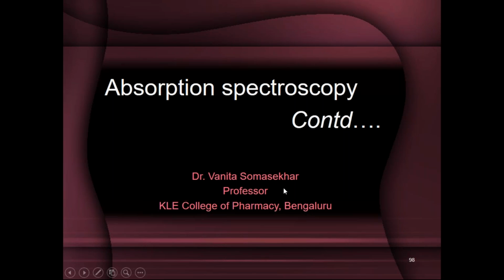We also had the instrumental deviations, which generally lead to negative deviations. That means you will be recording an absorbance less than the actual. And this can be eliminated to a great extent because this is mainly due to the presence of stray radiation or due to the use of polychromatic radiation.